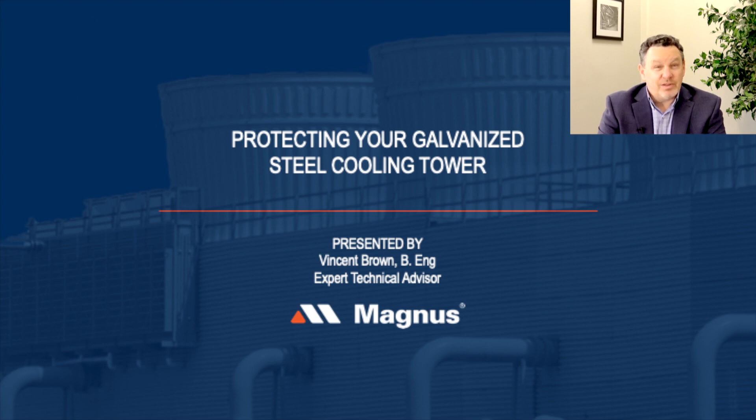The idea of galvanized steel gives the impression that it's very corrosion resistant, which is true because a lot of the galvanized used outside in the atmosphere is exceedingly well protected against corrosion over many years. But there's a difference between exposure to rain and sun and having galvanized submerged in water, especially industrial cooling tower water, where the zinc coating really does not provide very good protection against corrosion.